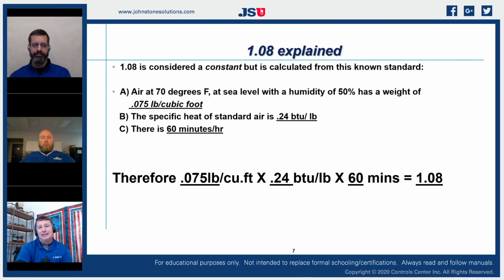The reason that I say that 1.08 is not a constant, you'll see this in many descriptions. They'll say that 1.08 is a constant. I will tell you that we use that as a common number, but it is not a constant at all. Here's where that is derived from. It is derived from the standard of air, which is what we consider the air that is in our breathable atmosphere at 70 degrees Fahrenheit at sea level with 50% relative humidity.